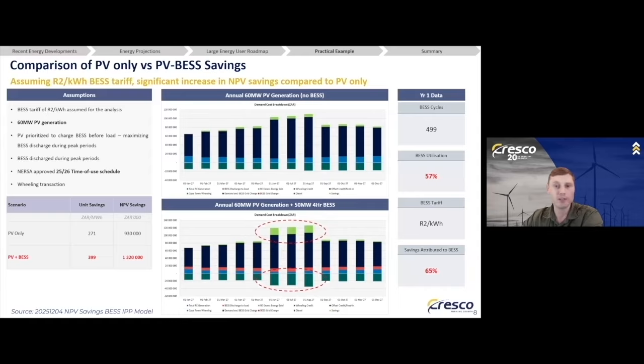But once BESS is added to the system, you can see that there's a clear reshaping of the demand cost stack, particularly in the winter months where the peak period grid purchases are materially reduced. So by adding the BESS, you're driving unit savings up from roughly 270 Rand per megawatt hour to close to 400 Rand per megawatt hour. And you're also significantly increasing the total NPV of savings.